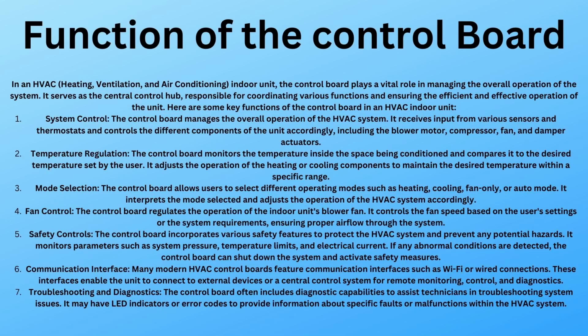Two, a lot of indoor fan units, or the blower motor as they call it, have different levels. You might have high, medium, low, and then that's it. They have different settings on these blower motors depending on the manufacturer who actually manufactures the blower motor. And then it could be an individual like Lennox has their own, or you get a universal blower motor, and then they'll have different settings. But you will know what settings you need to do on that blower wheel, and we will go over those types of issues in another video.